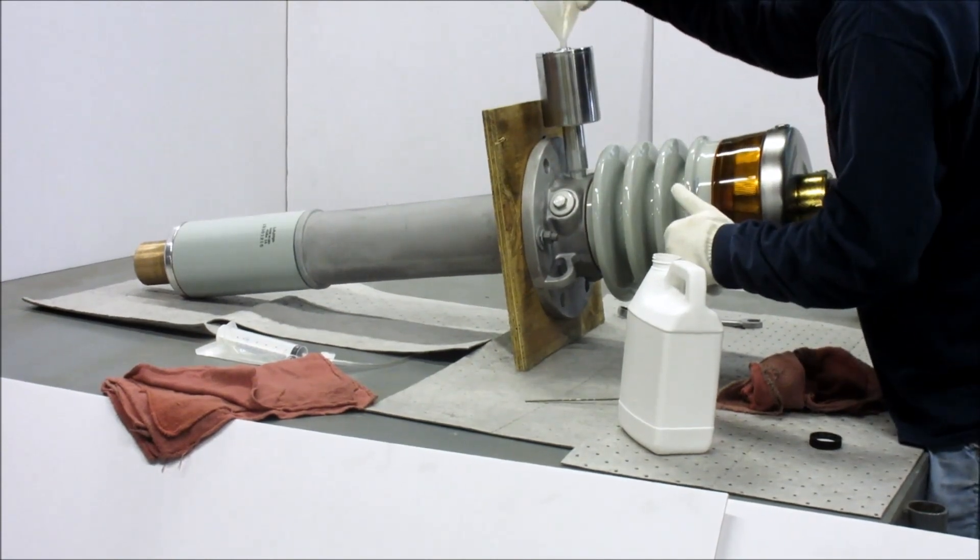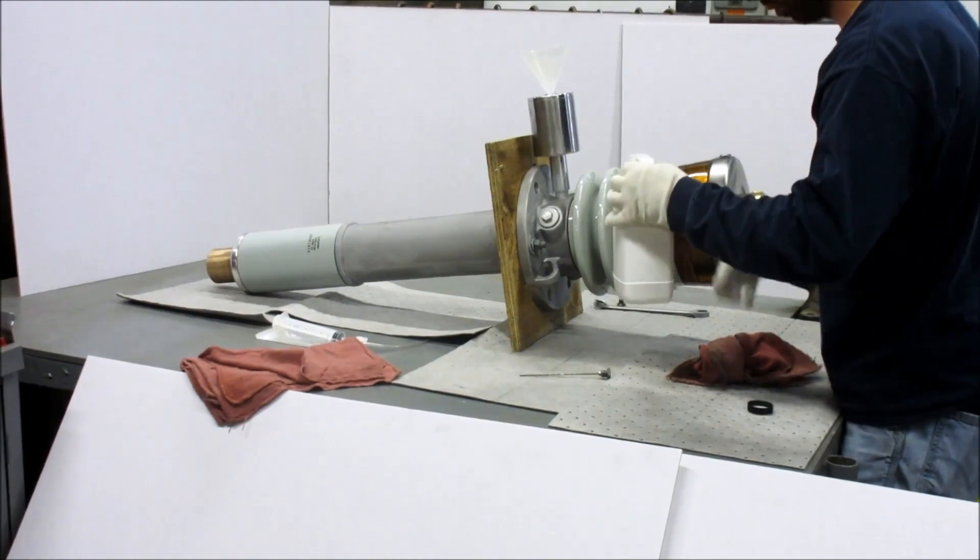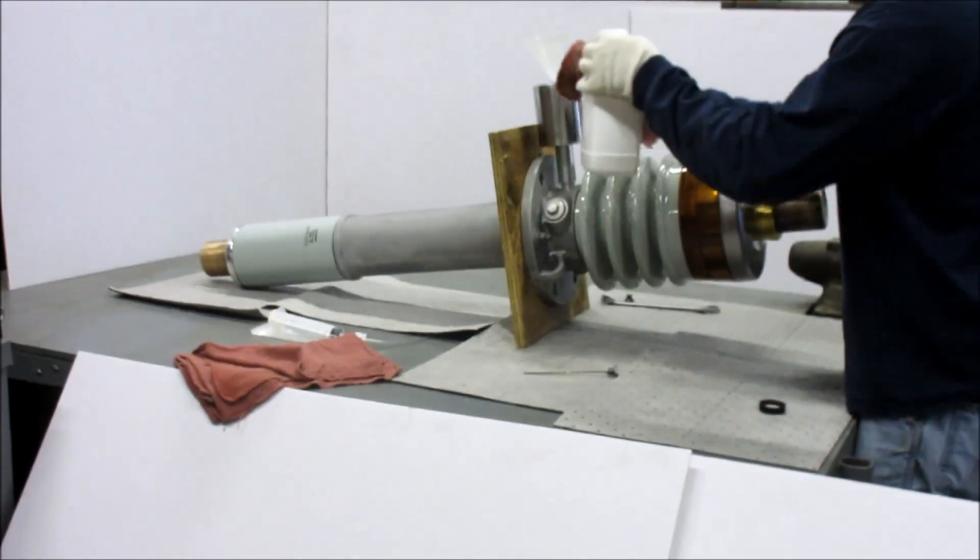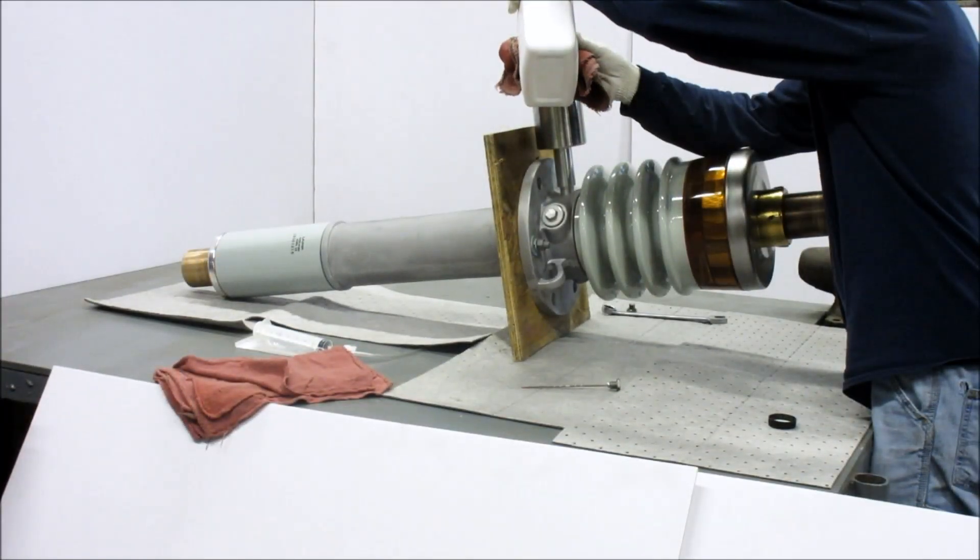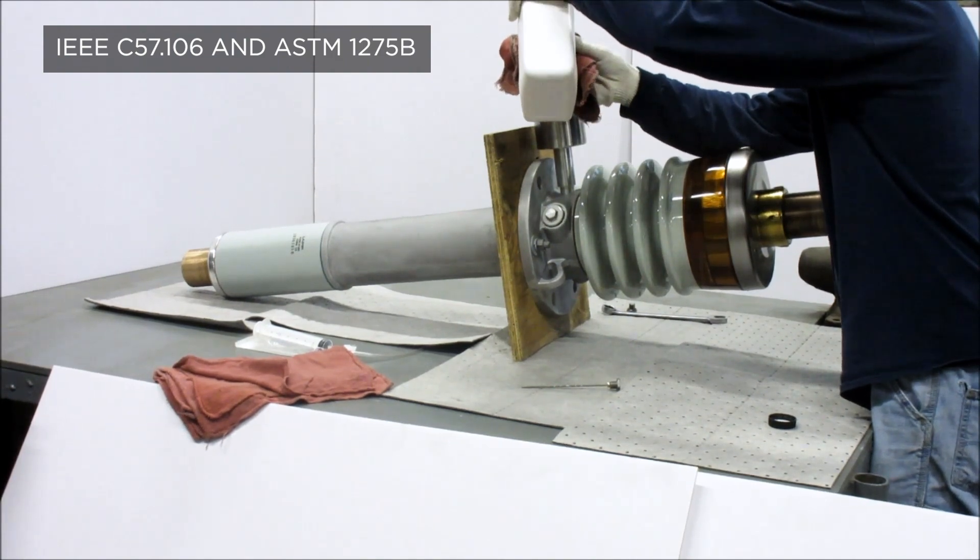Using a clean funnel, add oil to the reservoir. Use the extra oil supplied with the bushing or any non-PCB type 1 or type 2 transformer oil. The oil must meet the minimum requirements for new transformer oil per IEEE C57.106 and ASTM 1275B.